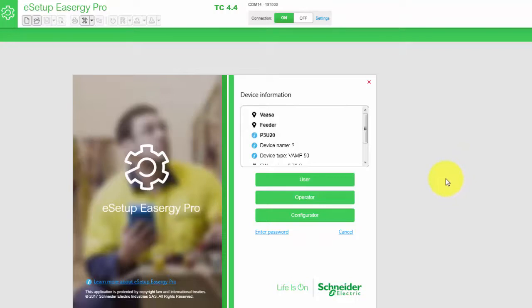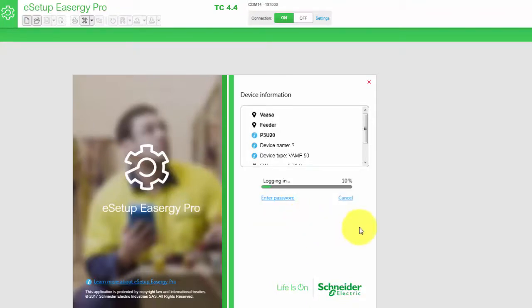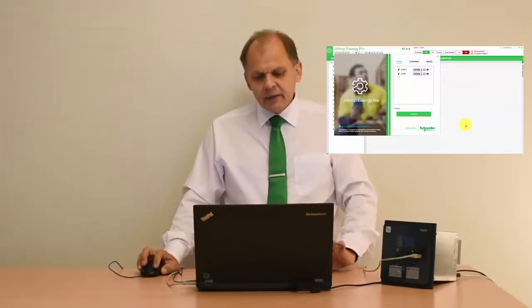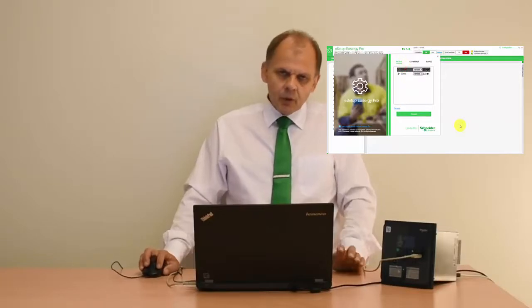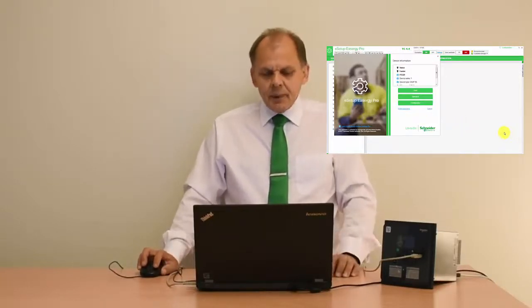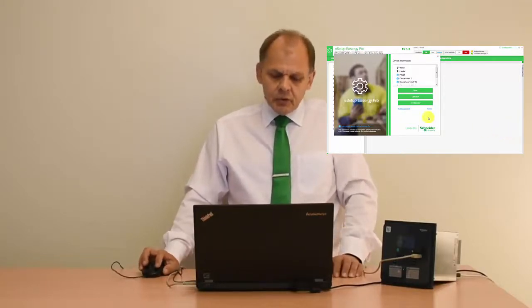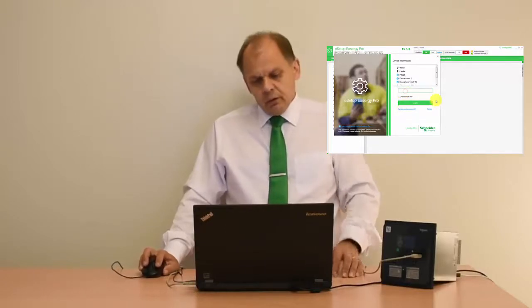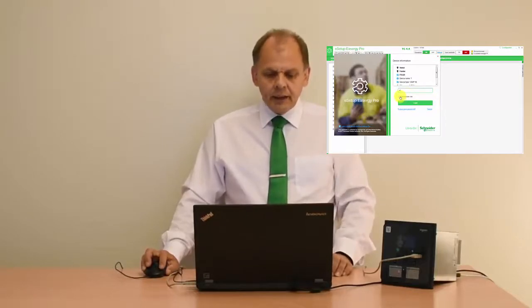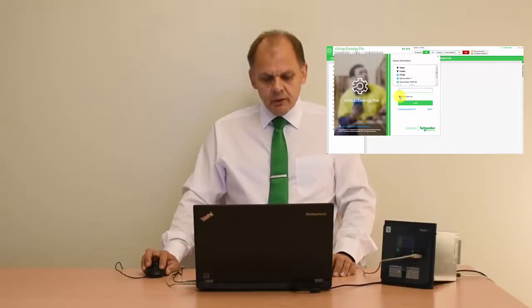By default when the relay is delivered from the factory there is a predefined set of passwords. User has no password, operator has the password '1', and configurator has the password '2'. If we select the configurator level it will prompt for password '2'. In case the factory password has been changed, we need to enter the correct password — we go to the same connection, select the same COM port, and choose Connect. We can also click to have future connections remember the new password.